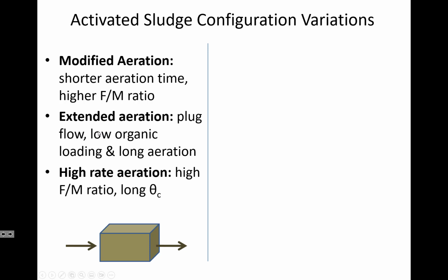And then the amount of plug flow performance, like how closely the reactor mimics perfect plug flow performance, because remember, no reactor is going to get there all the way. We have to add in baffles, and we talked about this earlier in the semester. The way that you can nurture plug flow reactor performance is by having diffusing baffles that make the water spread out in all directions rather than just having short circuiting between two pipes connected to a tank.